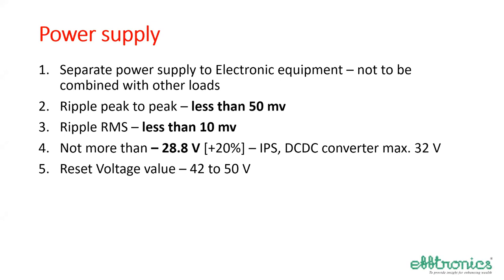Similarly, the power supply variation shall not be more than the permitted limit. Normally it is plus 20% and minus 10%. So plus 20% is 28.8 volts. Many times IPSs can give up to 32 volts, so we have to take care of that. Of course, the reset voltage for the axle counter is 42 to 50 volts. That is one of the limits.